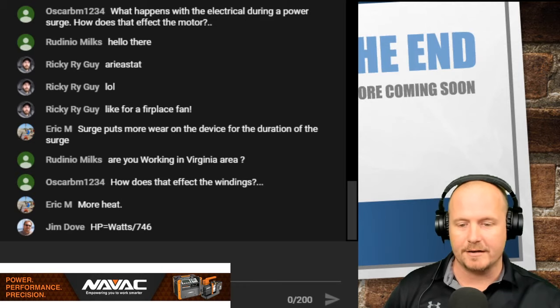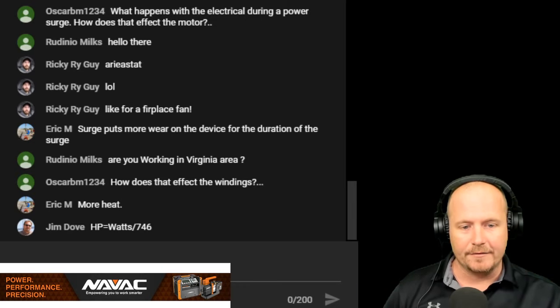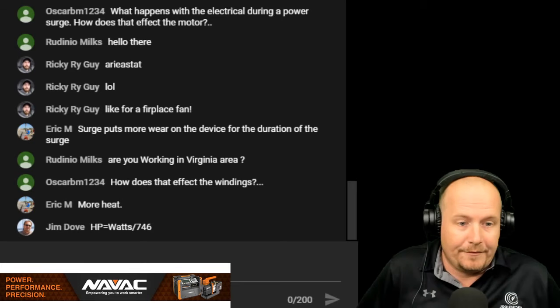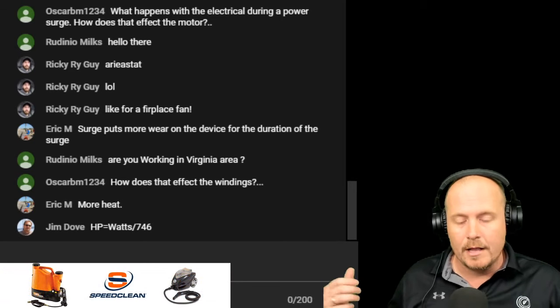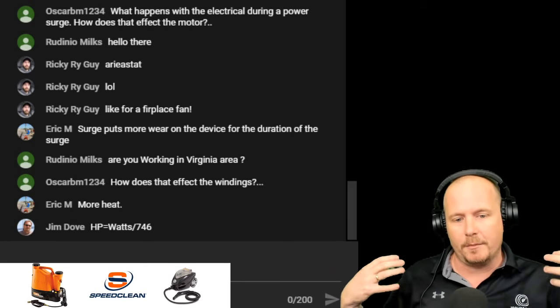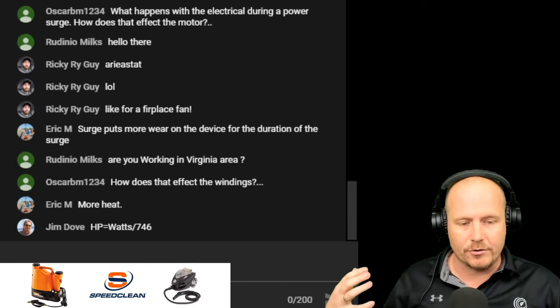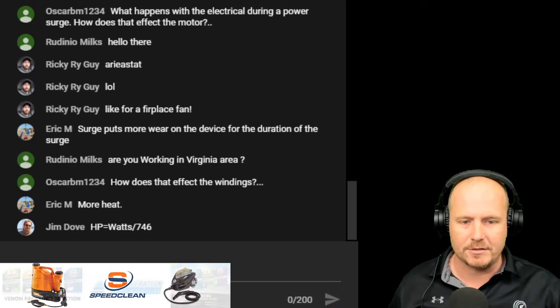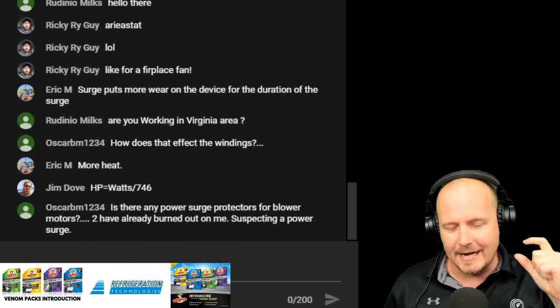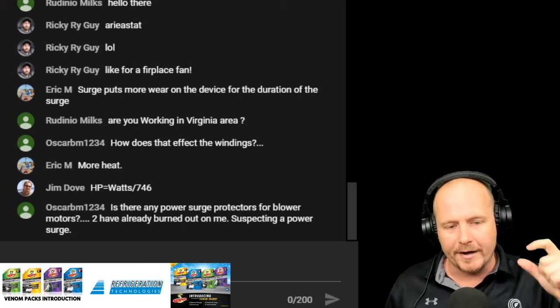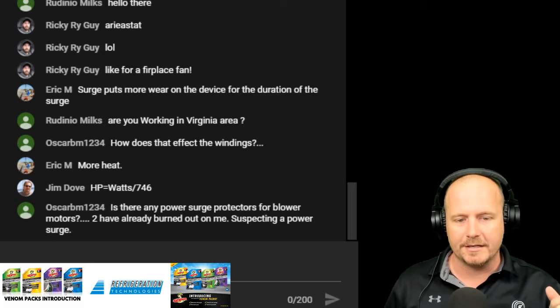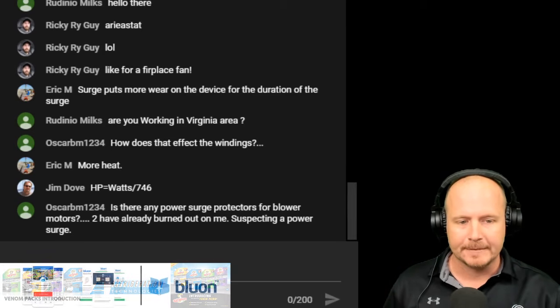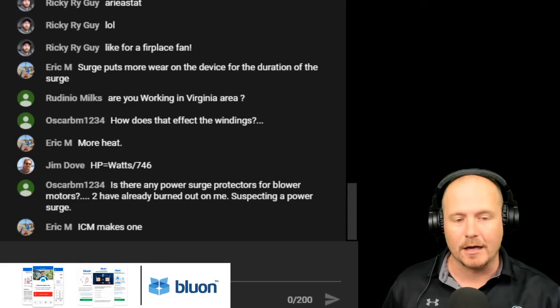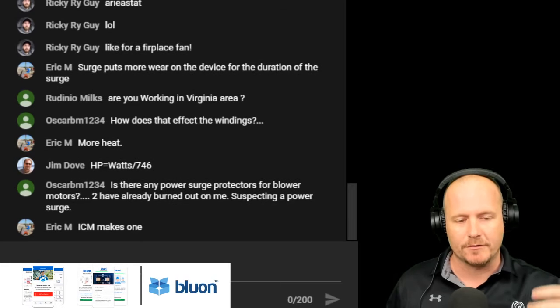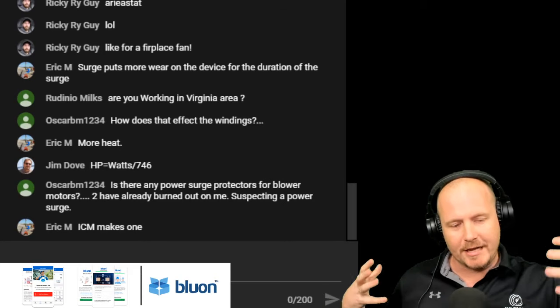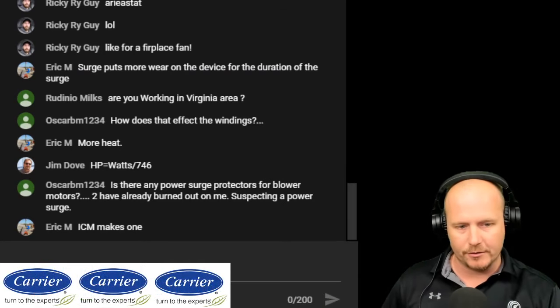When you have an increase in voltage, you're going to have a spike in current as well. But generally speaking, when you talk about a power surge like a lightning strike or something from the distribution power supply, that's usually an instantaneous surge, and those are very quick. The only way to prevent those is to have some sort of metal oxide varistor type system, some sort of surge protection system in order to help grab that current and shunt some of it to ground.